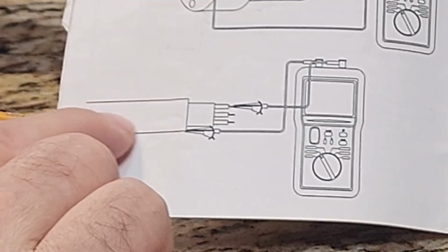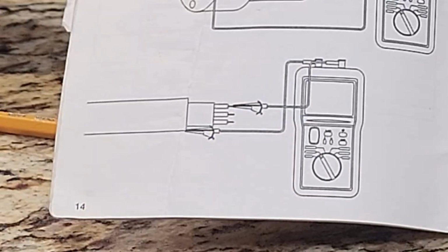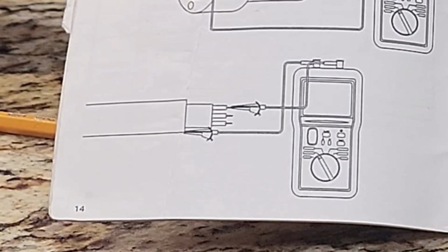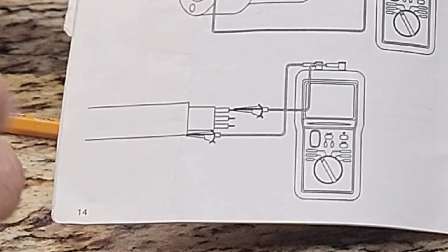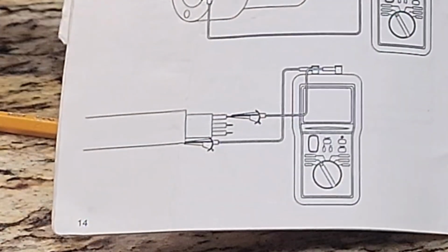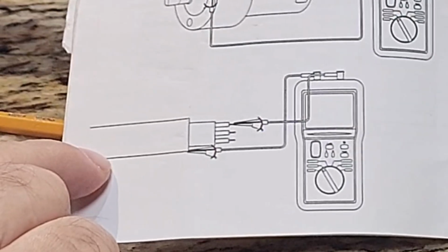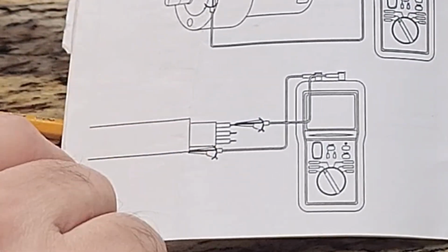Let's say this is an underground conduit, like that service we were going to upgrade at that facility, and we pull in the underground conduits. Well, before we energize, we want to make sure none of these wires' insulation got nicked. If it got pulled or dragged on the ground and somehow came in contact with the conduit, the only way you can figure that out is with a megohm meter.